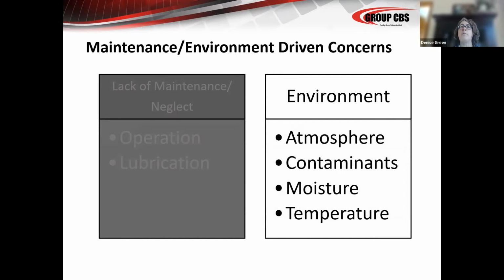So is it in a moist atmosphere? Are you in a water treatment facility where there is a lot of chemical component in the air, hydrogen sulfide, those kinds of things that break down components in switchgear? Are you in an area where you have a lot of dust, whether that be flour dust, grain dust, metallic dust, carbon, coal, any of those things? That's going to impact the ability for the breaker to do its job, and also impact the breaker when it has to interrupt under a fault.